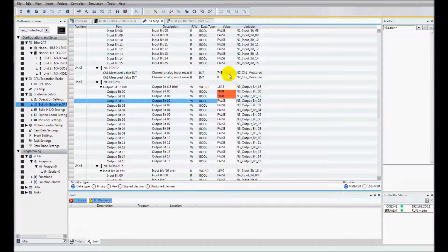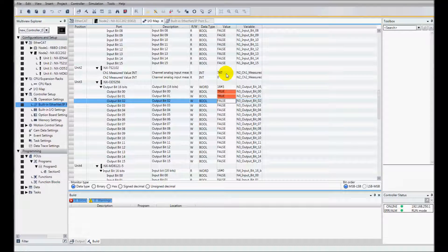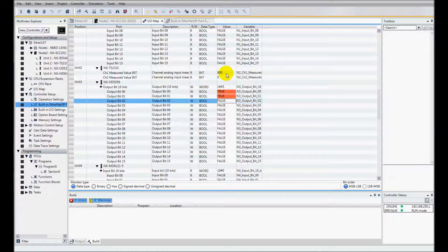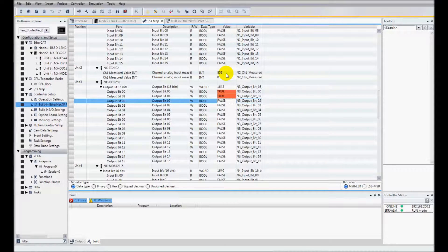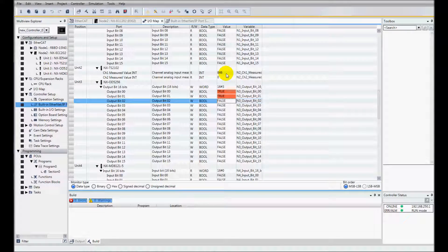I'll notice that my thermocouple card is reading 74.7. So that's my current temperature. I'm going to change that by putting my finger on the thermocouple and bringing that up. And that is how to add remote IO using Sysmac Studio.